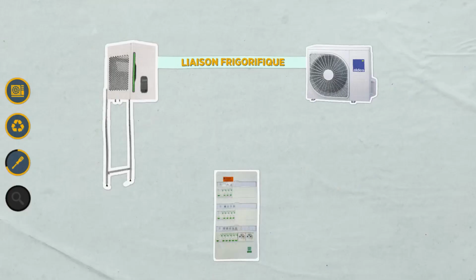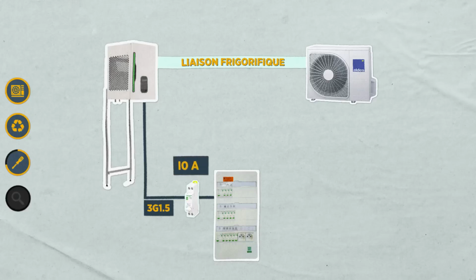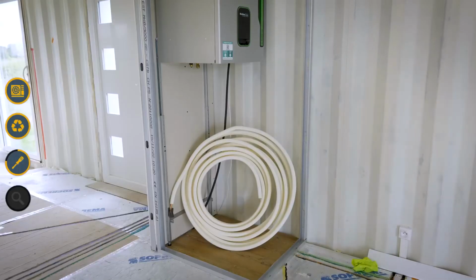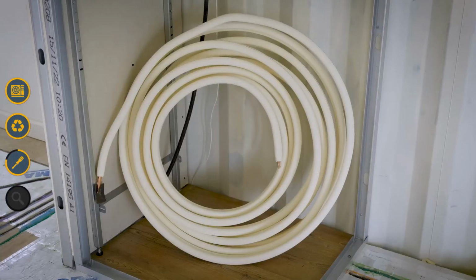On my indoor unit, I connect a 3-core 1.5 mm2 cable, which I link to my electrical panel on a 10 amp circuit breaker - that lets me power my indoor unit. Next, I connect another 4-core 1.5 mm2 cable to communicate with the outdoor unit on my roof. Finally, I prepare the refrigerant lines so that a professional certified by Aldes can come and do the final connection. Last step, the outdoor unit.